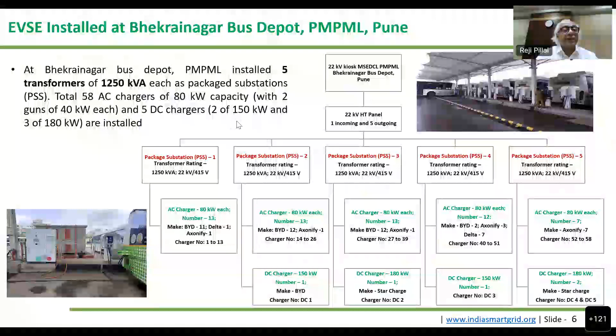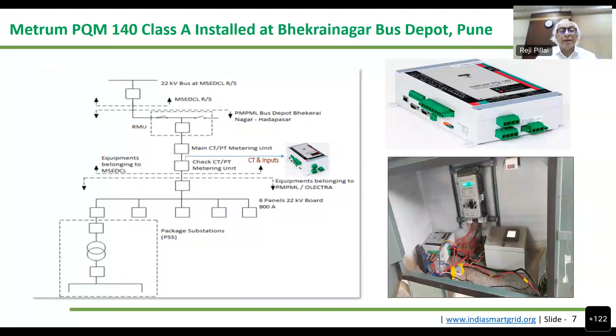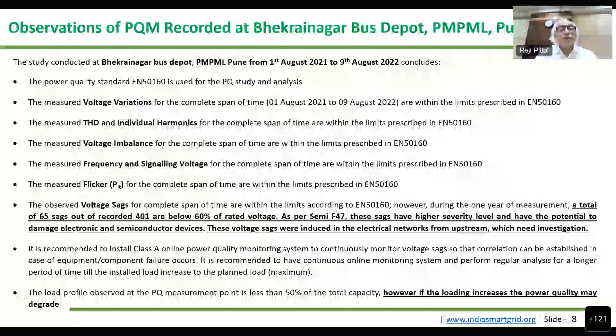The power quality meter which we deployed for this study is a Metrum make PQM 140 Class A from Sweden, taken on lease from Solvina. We are depicting the connection diagram here. The standard which we referred to for the power quality study and analysis is EN 50160. We found that voltage variation, total harmonic distortion, individual harmonics and voltage imbalance are all within the limits prescribed in EN 50160, as are flicker, frequency, signaling, etc.